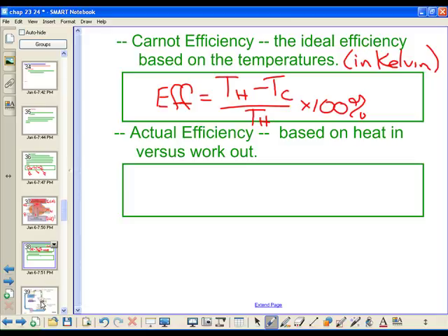But there was that operating temperature. So the high temperature was about 750, 800 degrees Fahrenheit. Through that system, in the condenser end, at the TC end, we draw a vacuum, so the temperature would always be down to 100 degrees Fahrenheit. So the steam at the end, because we are done at low pressures, would be 100 degrees Fahrenheit. So we try to get the maximum amount of energy out of those systems. A lot of energy there.